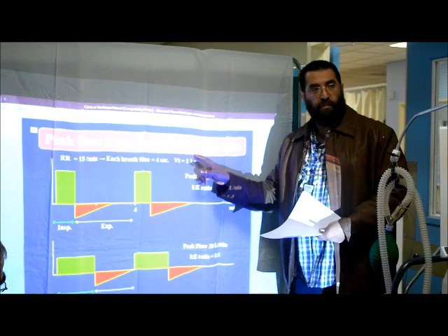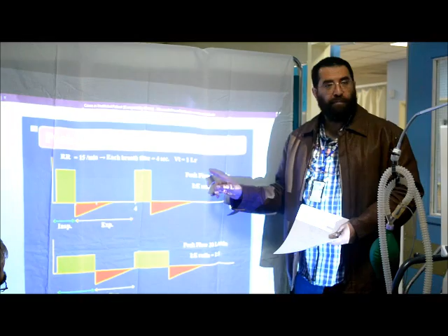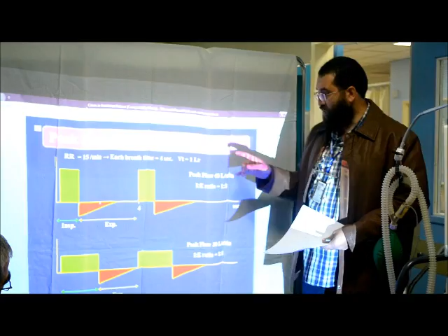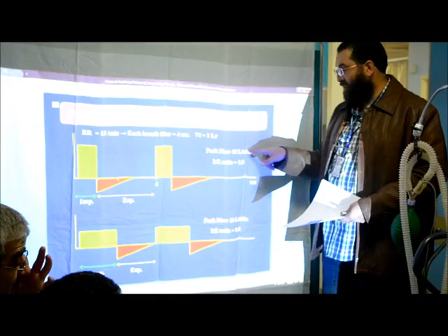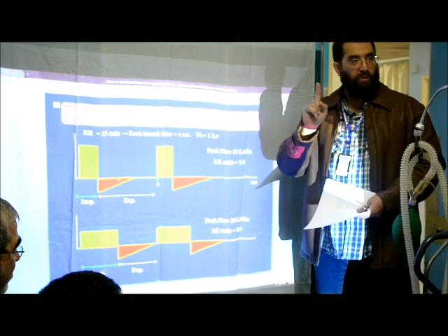Then, if the patient is adjusted for a tidal volume of 1 liter, and we adjusted the peak flow, what is the peak flow? Earlier we were saying, the speed of delivering the breath. How much is the speed which you will deliver? So it comes in liter per minute or liter per second. If it is 60 liter per minute, it means 1 liter per second. This is the speed with which we can deliver the breath.